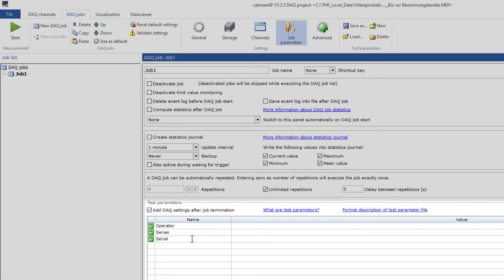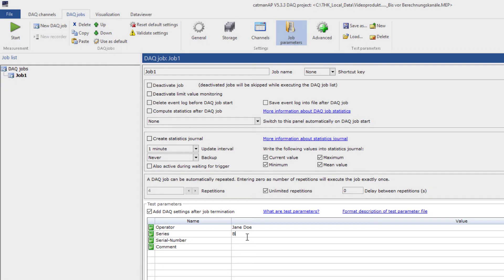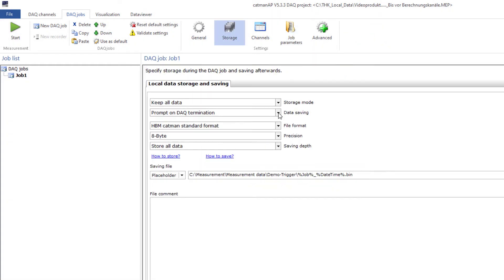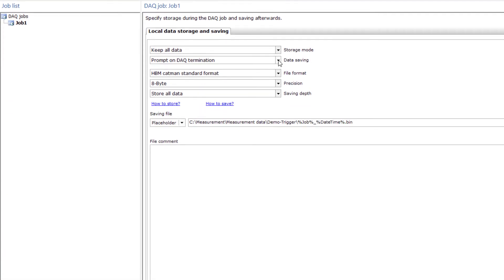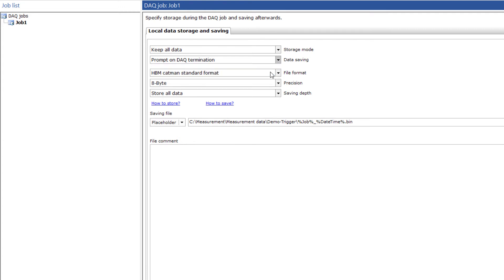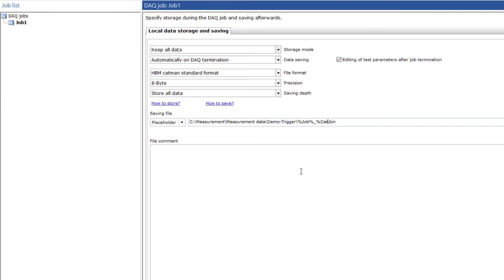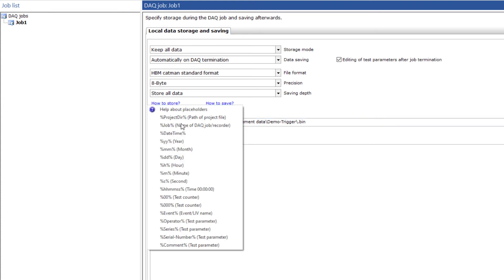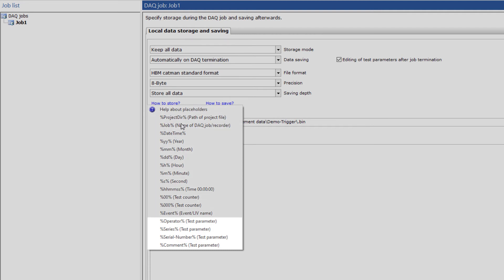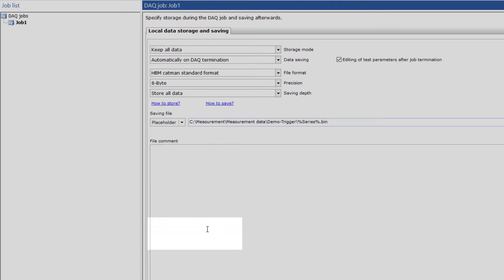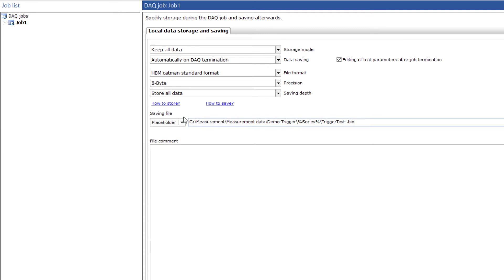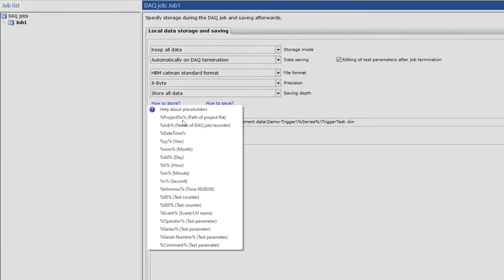I'll also define several test parameters so that I can clearly assign the measurement results later: Operator, Series, Serial Number, Comment. I can already pre-define the values that I know are unlikely to change. The data saving should be done automatically at the end. However, I would like to edit the test parameters. The measured value should be stored in the Catman standard format. Below, I'll specify the storage path and file name. I'll use a suitable placeholder to assign proper names to the tests. Here are also my test parameters. I'll use the Series as the path and the Test Counter to number my tests in a meaningful way.